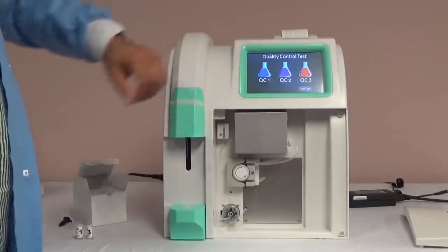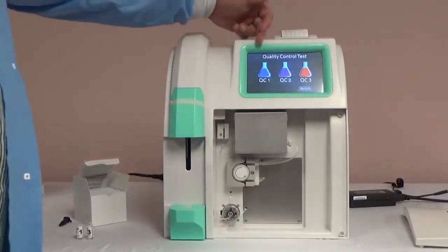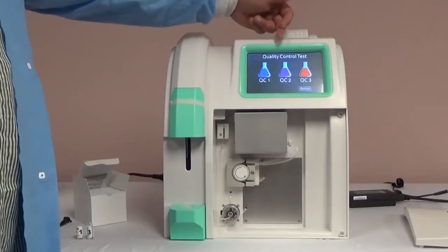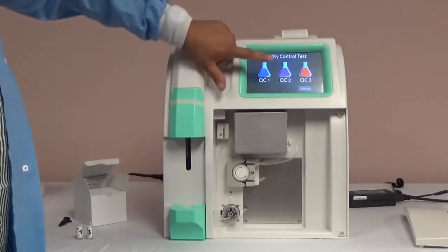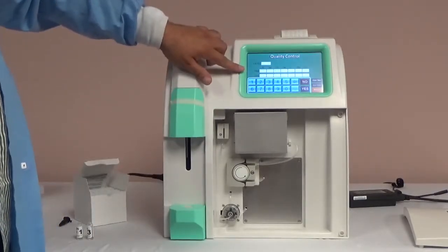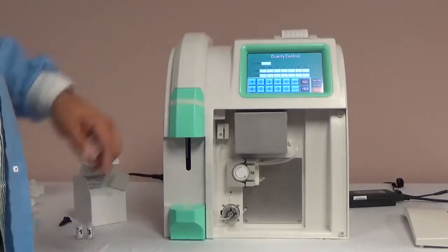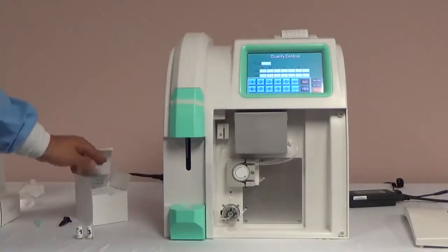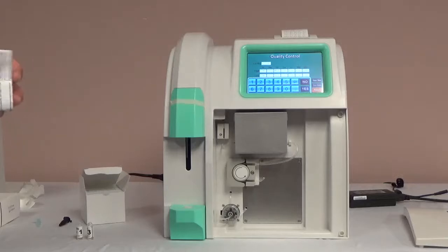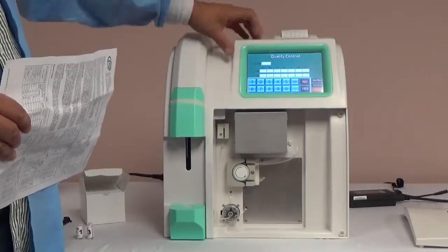You will return to the QC analysis screen and begin running QC. You will begin testing by level. Select the test, QC level 1, 2, or 3. You will enter the high and low target for the range for each level. You can get this information from the insert sheet. The first thing you will do is enter the lot number, followed by the high and low target for each electrode, and then hit Start Test.